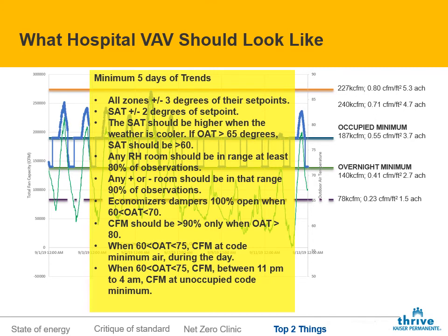Here's a set of acceptance criteria. First off, all the zones in the building need to be plus or minus 3 degrees of their set point. That's our acceptance criteria for zones. Second, we should see supply air temperatures plus or minus 2 degrees of whatever the set point is. We do expect our systems to have supply air resets. So when the weather is cooler, we should have supply air temperatures at 60 degrees, and then when the weather's warmer, your supply air temperature should drop down.